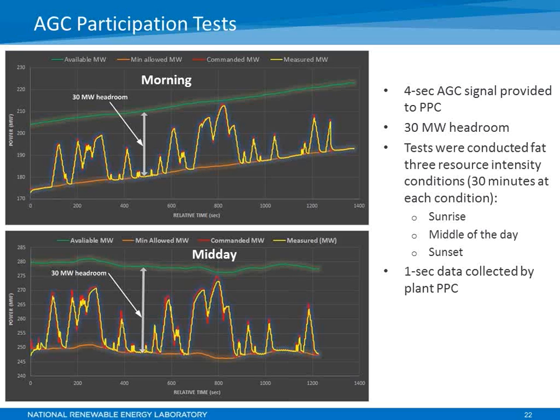On top of that, the actual AGC signal, well, I take it back for a second. The historic AGC signal that California ISO provided to a conventional power plant of a similar capacity was provided to the power plant controller to evaluate how well it can follow the set point signal. The decision was made not to feed the actual AGC signal in there in order not to cause any disruption in existing market operation. So the red trace in there is the commanded AGC set point from historical data, and yellow is the actual power measured at the plant terminals.